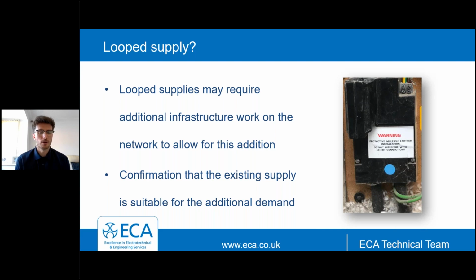So something else to add around the notification side of things. When you visit the site and look at the supply parameters, you may find that you have a loop supply. Again, this is going to require a conversation with the local distribution network prior to the works being conducted. So even if that demand is going to sit below the 60 amps, the notification to the DNO in this case is going to have to be before, because of having the loop supply. Loop supplies may require additional infrastructure work on the network to allow for the addition. So the DNO needs to confirm that the existing supply is going to be suitable for that additional demand. So in many cases, it could be a good idea to have the conversation with the supply network prior to the addition of the EV charging equipment.